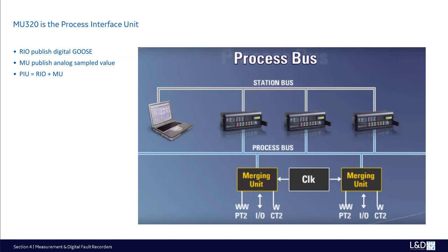As we learned in the IEC 61850-102 module, the process bus is intended to replace the hardwires between the ITs and the IEDs. There are 3 basic types of devices that publish data for process bus: merging units MU, remote I/O modules RIO, and Process Interface Unit PIU. RIO publishes equipment status in GOOSE messages.